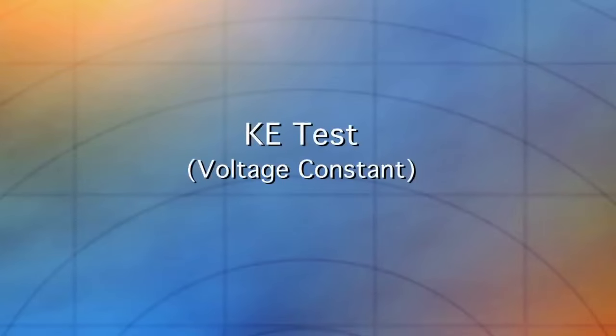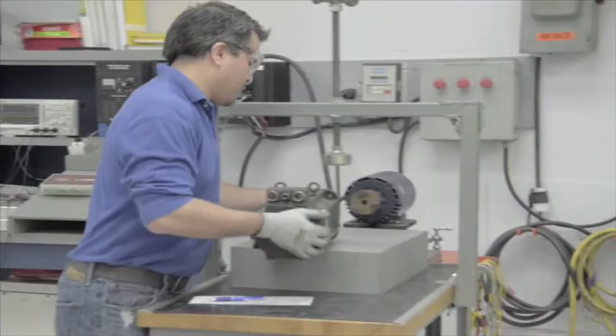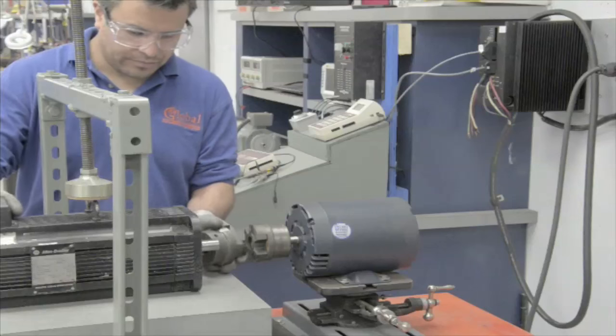The technician is now moving to the KE testing station. The KE test tests the condition of the magnets inside the motor. If the magnets are good, there won't be any problems with the torque. If the magnets are weak or broken, then torque is lost.